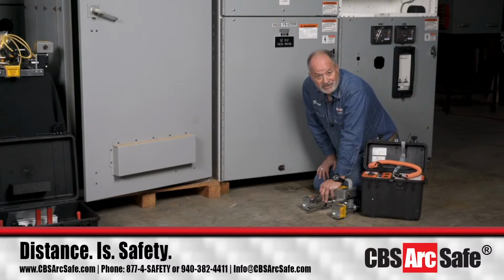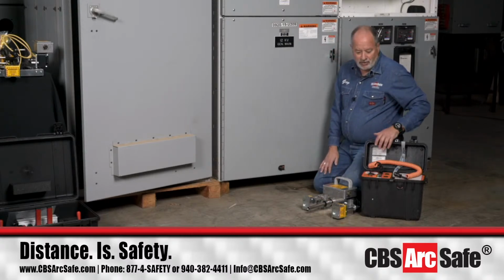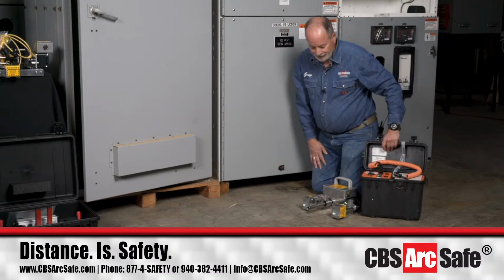So if you've not done maintenance on your switchgear, our remote racking equipment isn't going to fix your lack of maintenance. It may help identify the fact you have not been doing maintenance, because you may be having to use higher values to get things in and out. But that's what it's telling you right there: if your equipment's not using the normal torque values that we set, you probably need to get maintenance done on your switchgear, and that's going to be one of the first indications of it. Do we have any other questions, Kyle? So far, that's it. Okay.